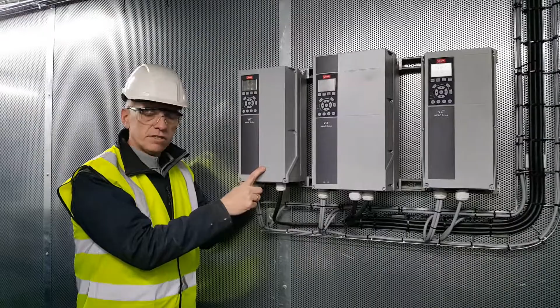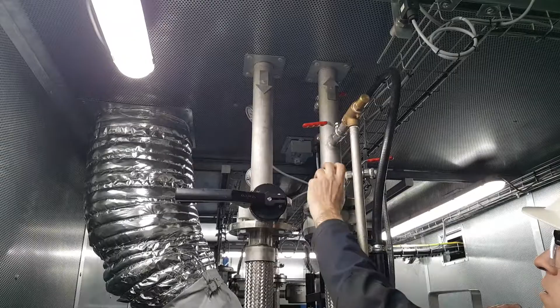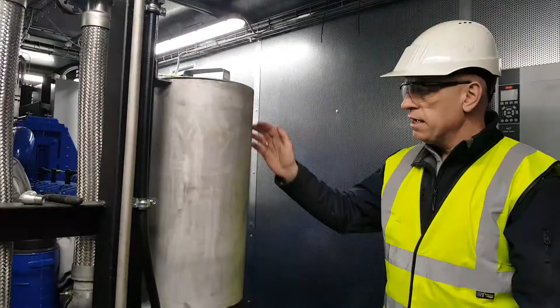With the jacket water pump, we manually throttle it down to 41, 43, 45 hertz, whatever it is, and fine tune that during commissioning so that the differential temperatures on the jacket water in and out are as per design, and then we know we have the right flow.